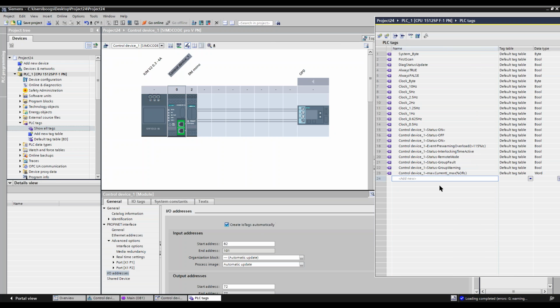It created the tags for my SIMOCODE for on, off, or this could be clockwise, counterclockwise, forward, reverse, my overload, my interlock time, remote mode, meaning is the PLC in charge or is somebody locally running the pump, or group fault, or group warning, or max current. So I've got all these tags already created. All I did is check that box and I'm done. Now what happens if I need to add some more to those tags? Or you ask me, hey Mark, where do these tags come from? So I'm going to go here to my SIMOCODE.